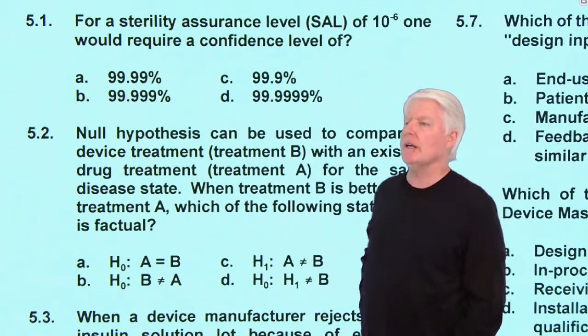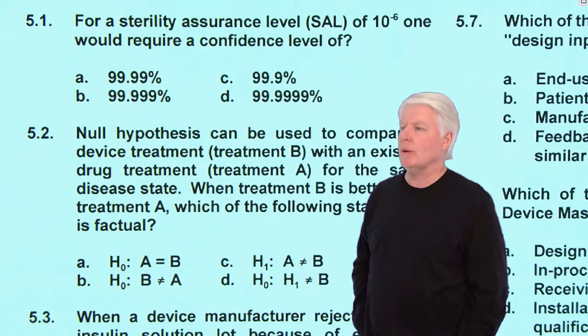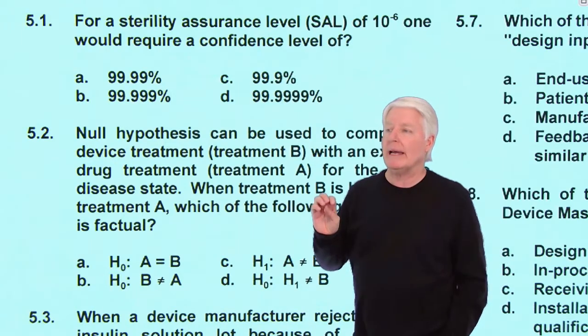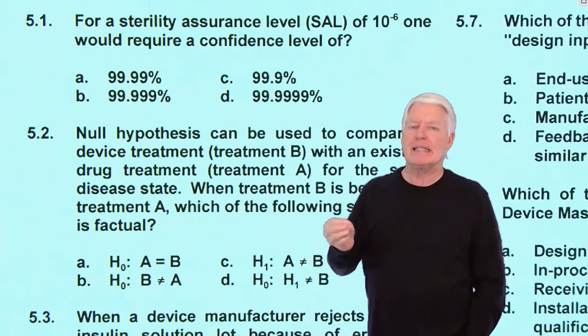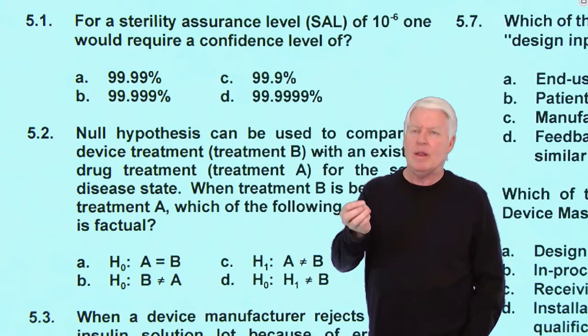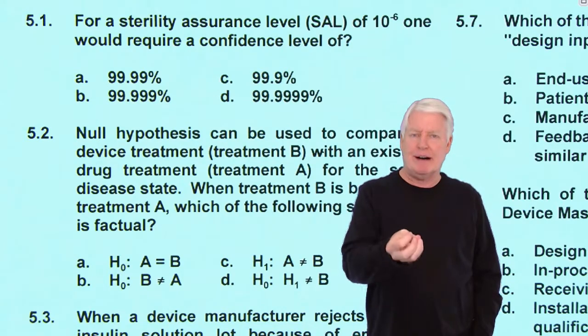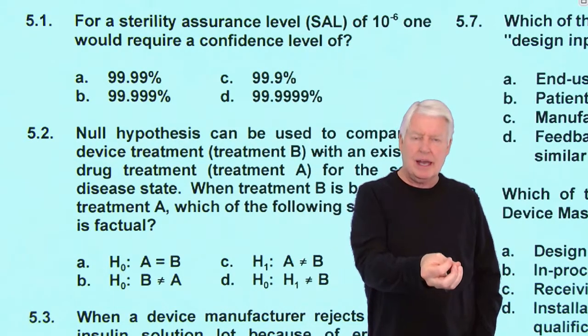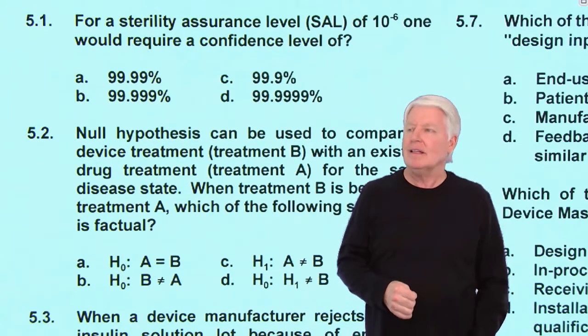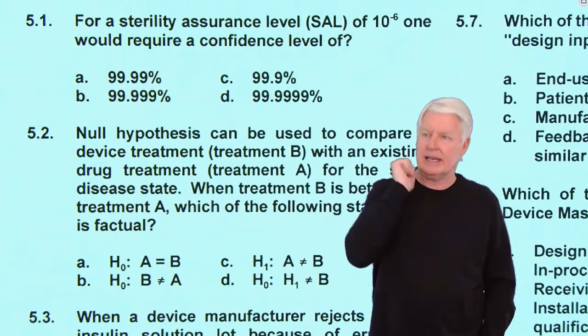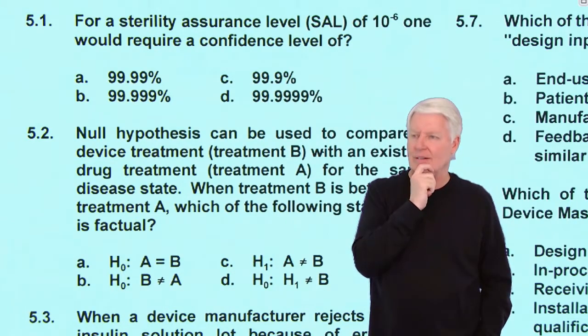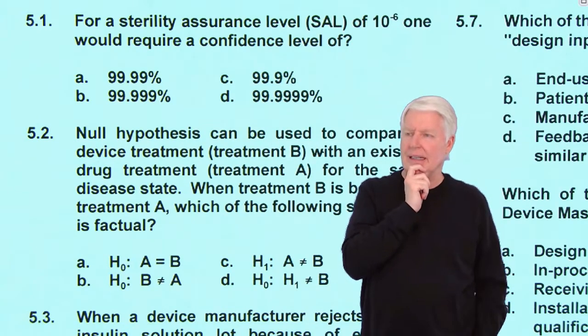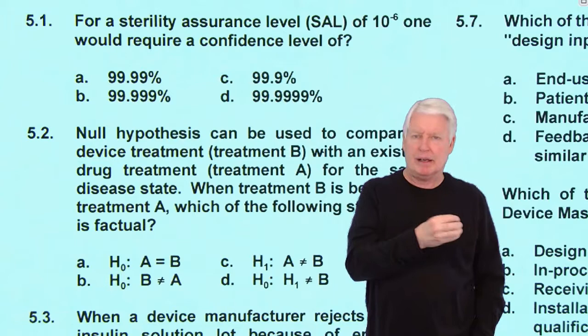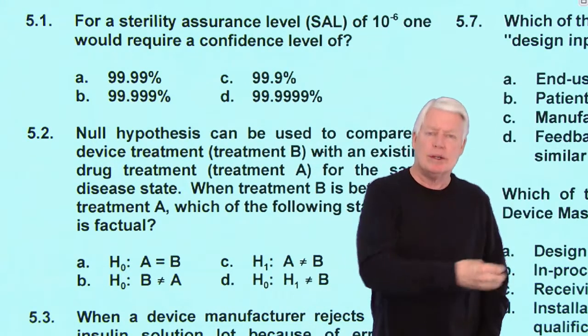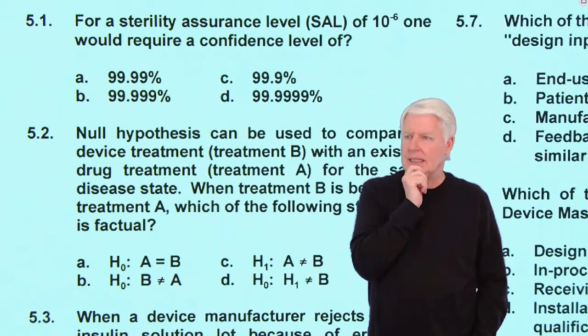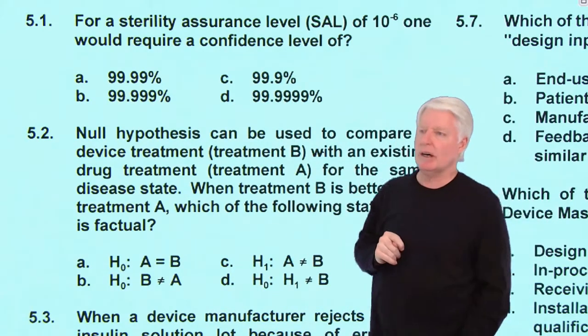Question one: for a sterility assurance level, or SAL, of 10 to the negative 6, one would require what confidence level? Remember, SAL is the probability that a given sterilized device would go through the sterilization process and not be sterilized. In this case it's 10 to the negative 6th. Every organization has a different SAL level, but 10 to the negative 6th is considered pretty high, meaning one part per million of products that go through sterilization would not be sterile. That would be acceptable for this company.